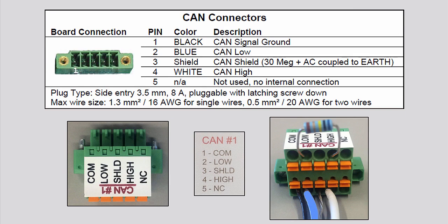Wiring of the CAN port should be as follows. Wire the black cable to pin 1 — this is the CAN signal ground. Wire the blue cable to pin 2 — this is the CAN low signal. Wire the shield to pin 3. Wire the white cable to pin 4 — this is the CAN high signal. Pin 5 is left empty. A 120 ohm resistor must be used as a termination resistor at the end of each trunk line. This resistor is wired with one end in pin 2 and the other in pin 4 of the connector.